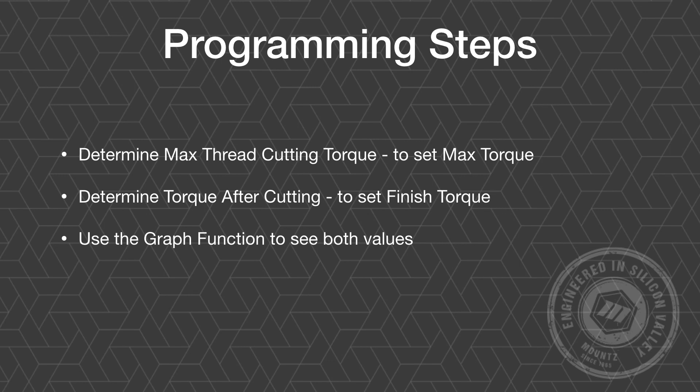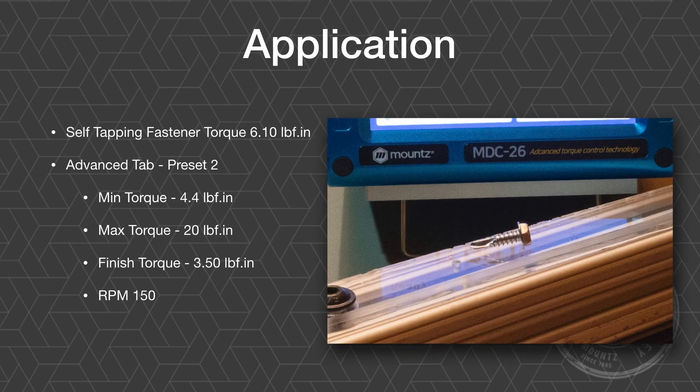In this application, we have a self-tapping screw going through a piece of plexiglass, and the final torque is 6.1 inch pounds. We have our min torque set to 4.4, our max torque set to 20, our finishing torque set to 3.5, with the RPM at 150. So once the system sees 4.4 it will switch into thread tapping mode, and once it sees 3.5 it will exit the mode and then look for the preset final torque.